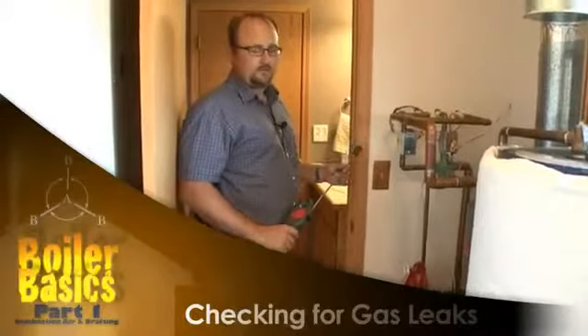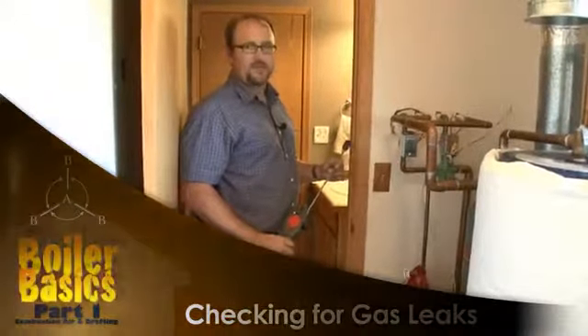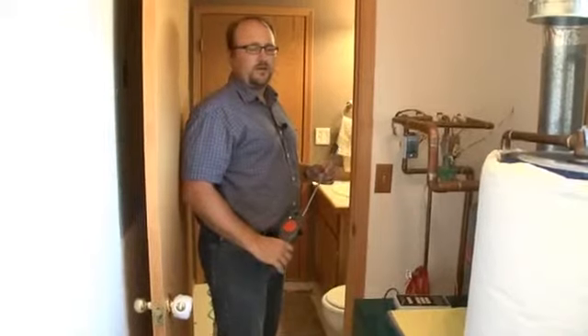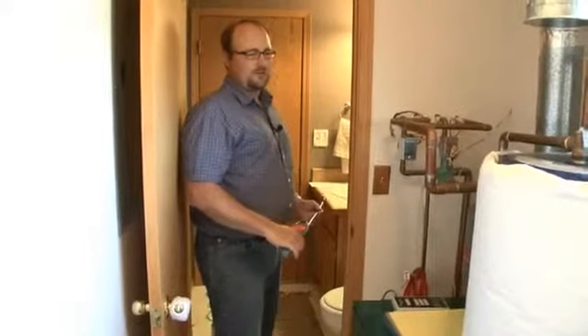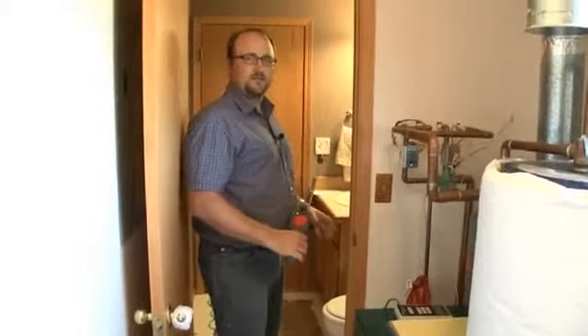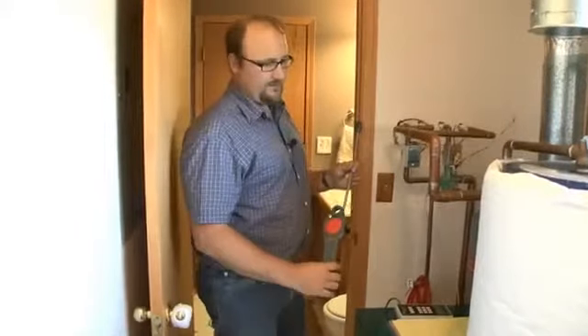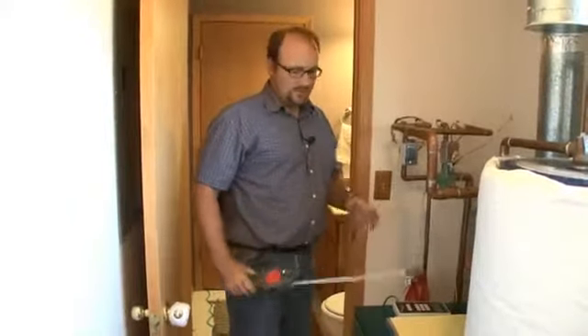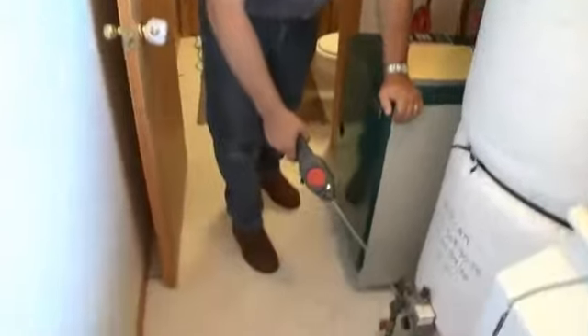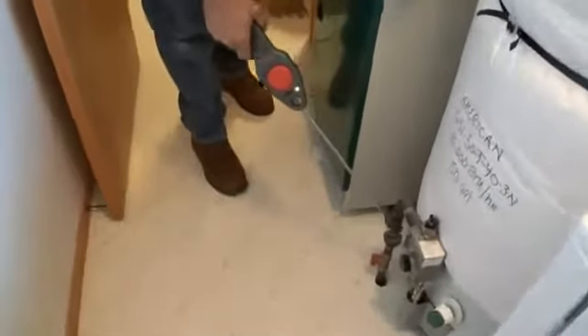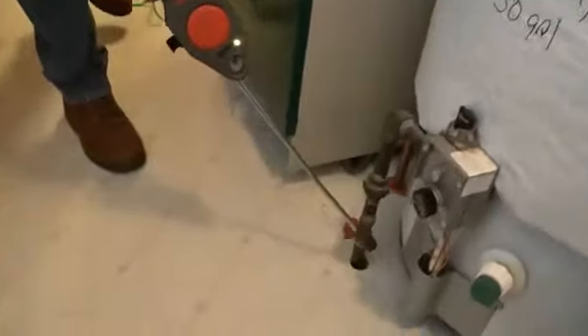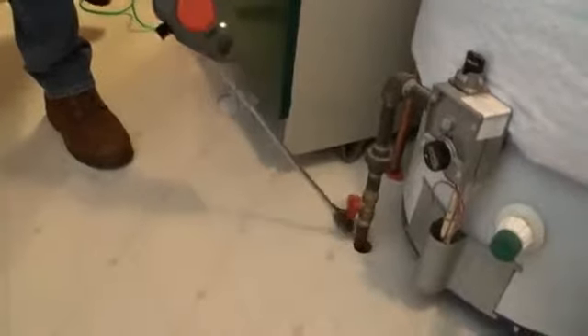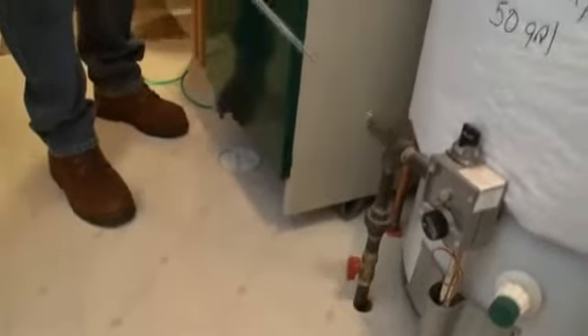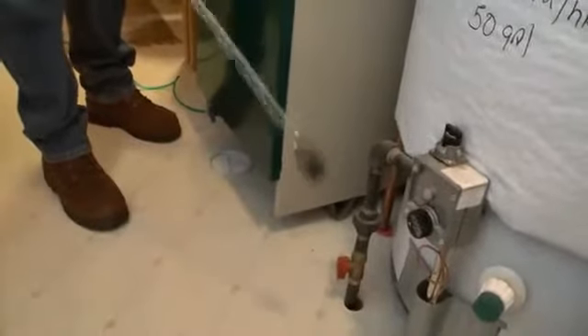Prior to doing any diagnostics work, what I want to do is check for gas leaks. I go down into the crawl space in this house, and use this leak detector to check for gas leaks down there, and check for gas leaks at the appliance. I basically do the same technique all the way through all the gas lines and make sure I don't have any leaks. If I do have leaks, I need to fix them before I continue with any of my diagnostics.